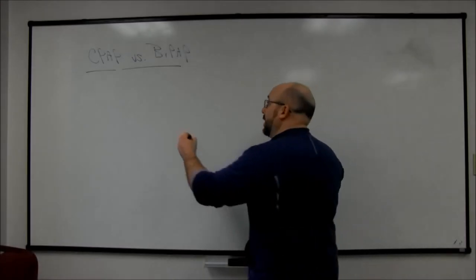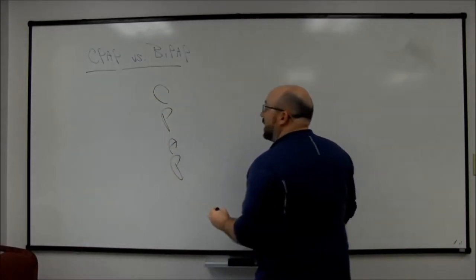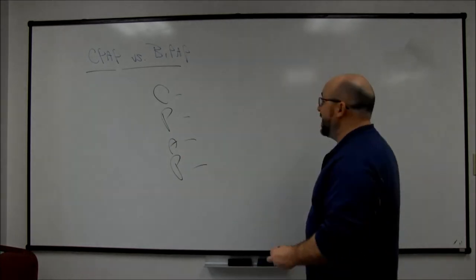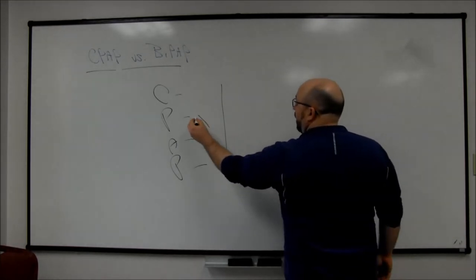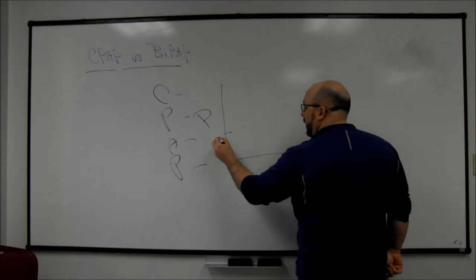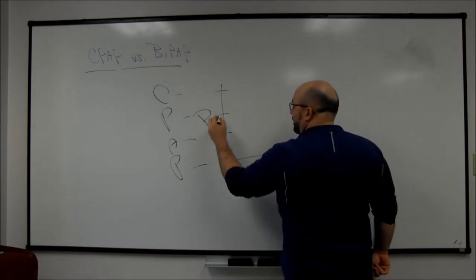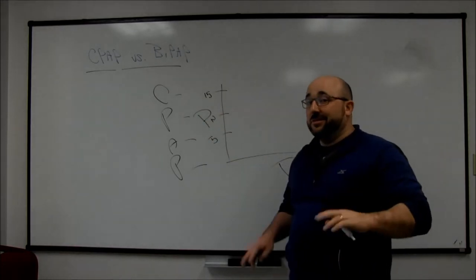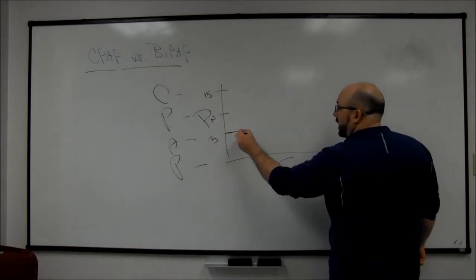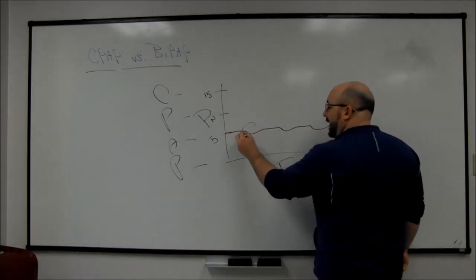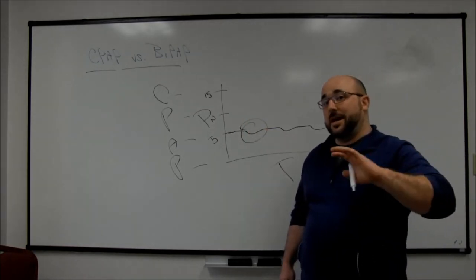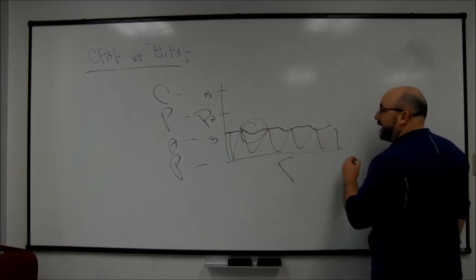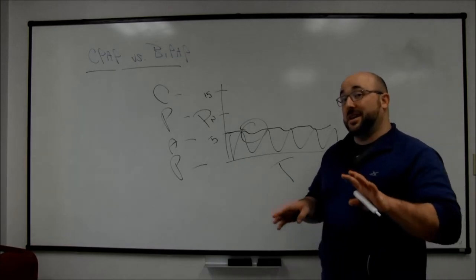Let's talk about CPAP first. It's an acronym: CPAP, continuous positive airway pressure. So one constant pressure continuously. The best way to show it is here on the pressure-time waveform. Let's say we have this set at 5, 10, 15 centimeters of water pressure. We set them on a CPAP of 5, this is pretty low. The waveform is going to look something like this: you see this constant pressure is maintained. These little dips right here are actually the patient actuating their own breath, but during that time they're going to continue to get this CPAP.